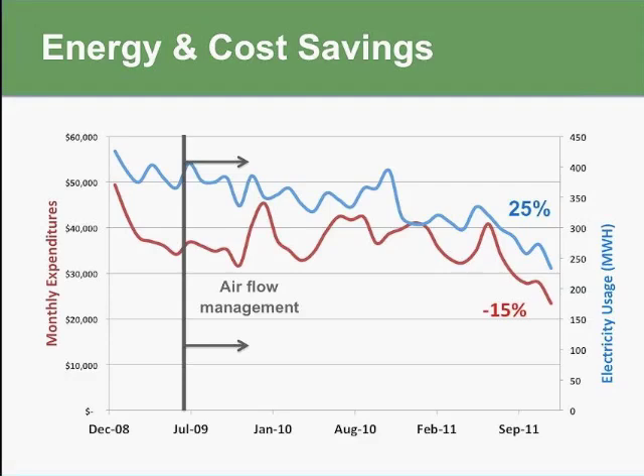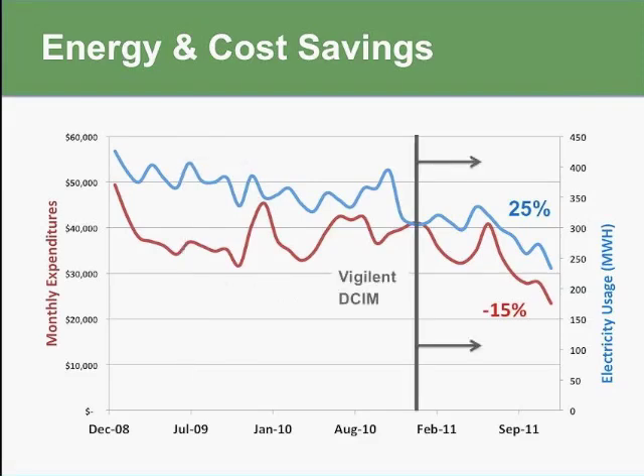However, it wasn't really optimal because we didn't know that we could reduce, say, the fan speed of the CRAC units or raise the set point temperature. That's where you really gain the energy savings and the cost savings. But when we implemented the Vigilent system in January of 2011, you can see there was a significant drop in both the cost and the energy usage as a result of being able to optimize the operations of the CRAC units and raising set point temperatures.